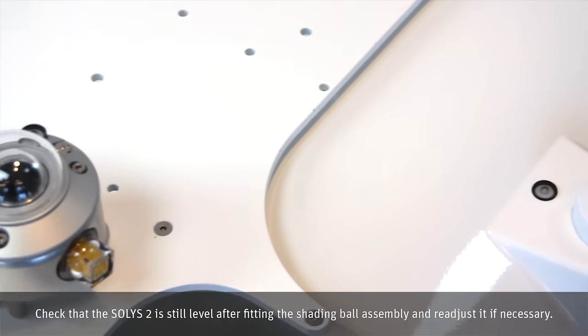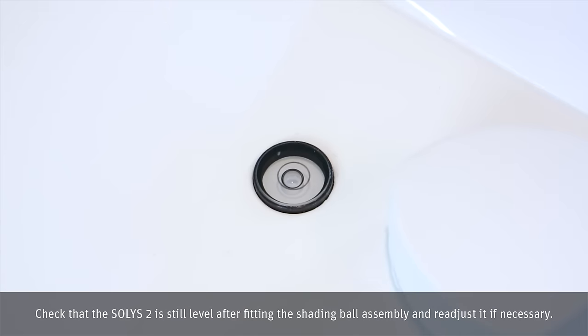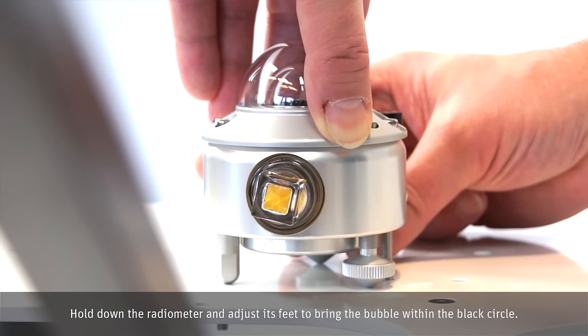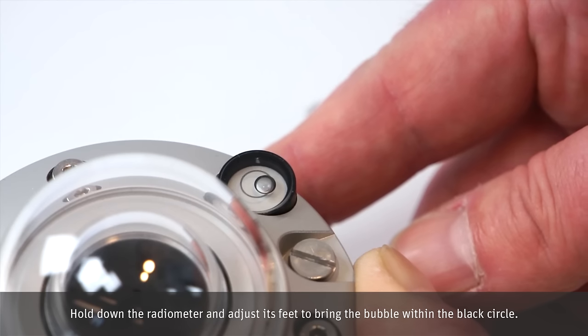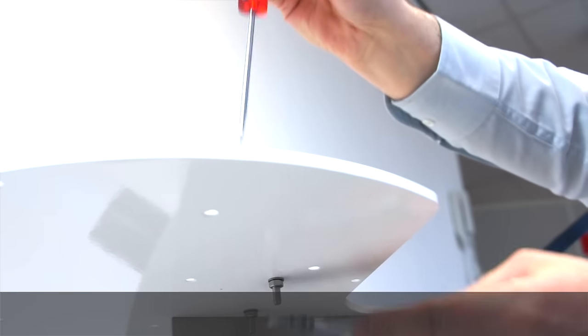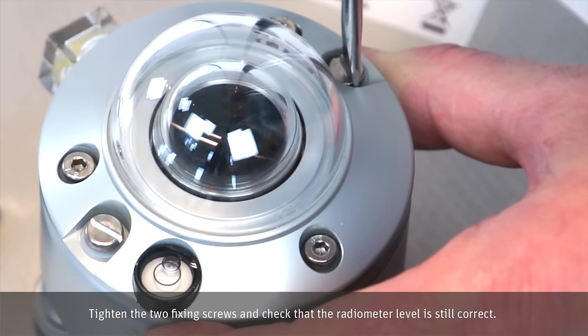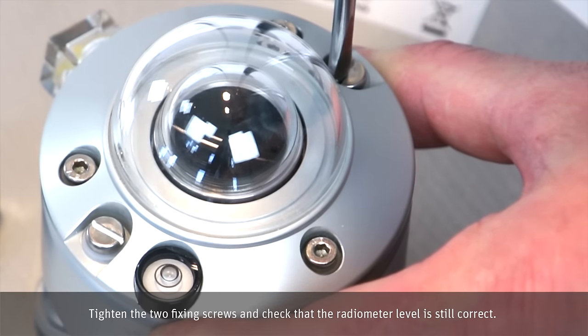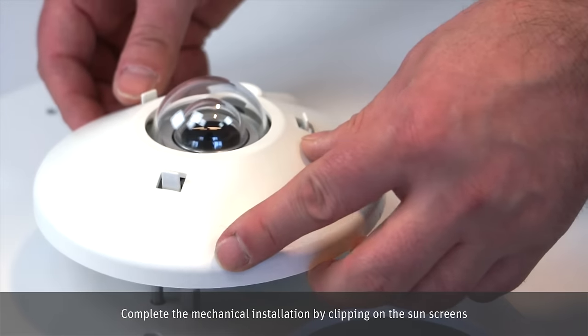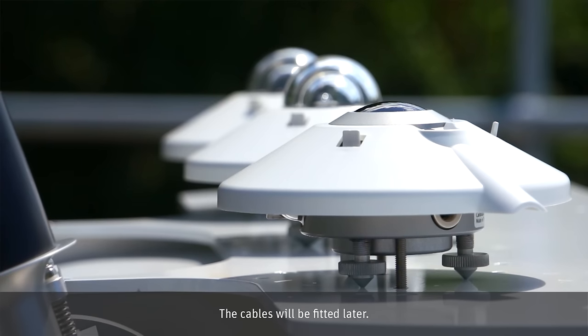Run up the nuts loosely. Check that the SOLYS 2 is still level after fitting the shading ball assembly and re-adjust it if necessary. Hold down the radiometer and adjust its feet to bring the bubble within the black circle. Tighten the two fixing screws and check that the radiometer level is still correct. Complete the mechanical installation by clipping on the sunscreens. The cables will be fitted later.